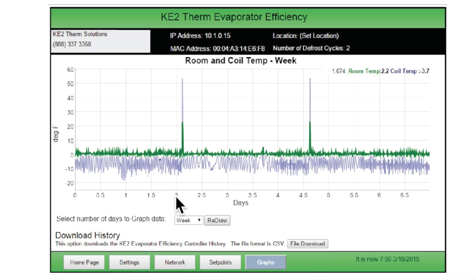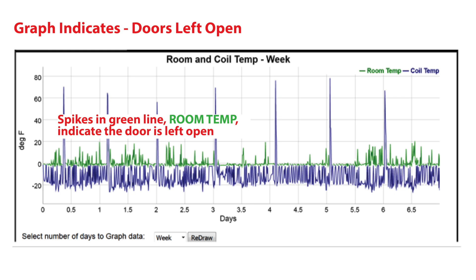The graphs are extremely valuable for identifying loading patterns, extended door openings, system issues including extended compressor run time, and the ability for the system to meet the temperature set point. In this example, we see by the multiple green spikes that the doors are constantly being left open, which will result in inefficient operation and potential coil icing issues.